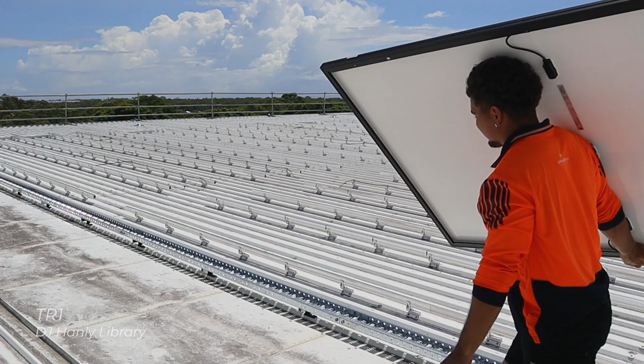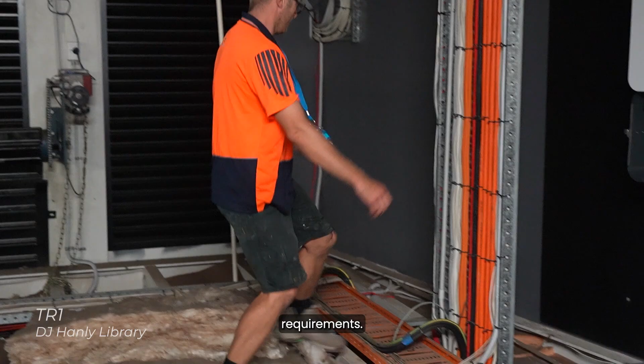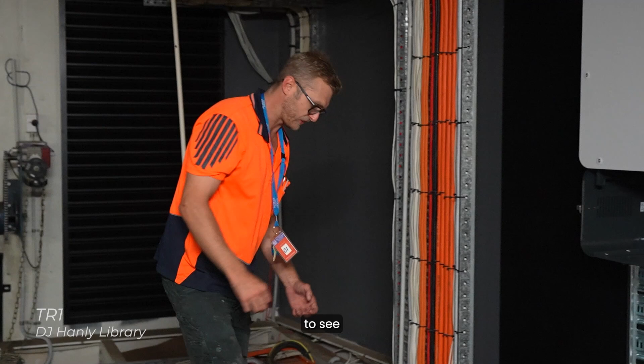This is our library building. This is our 110 kilowatt SunGrow inverter, and this is our PVD board - actually the master control for all 3 systems at Nudgee College. The grid protection relay talks over wireless relays across the 2 buildings to have all inverters simultaneously shut off as per Energex requirements. This is our main switchboard for the library building. Our PVD board is fed from that, so we'll have AC cables running across the tray, across this span, and down to fit off into that main switchboard. This is also where we'll have our energy meter to give consumption metering, allowing the client to see what they're using, what they're producing, and what they're either importing from the grid or exporting out to the grid, all in real-time values.